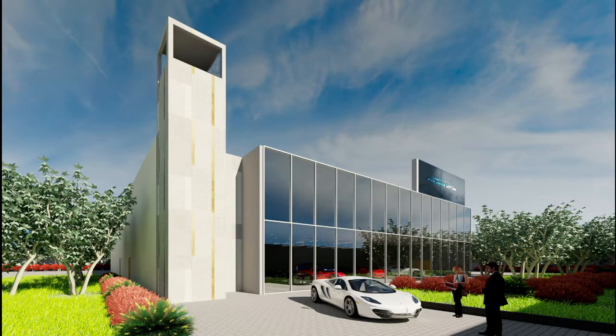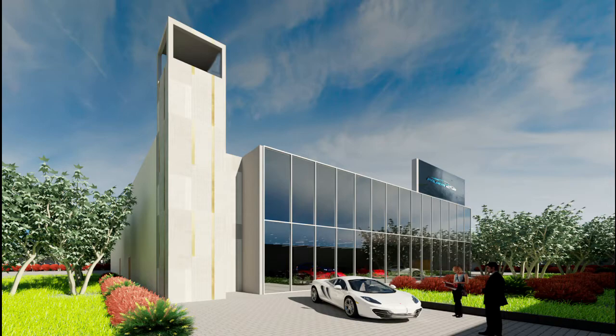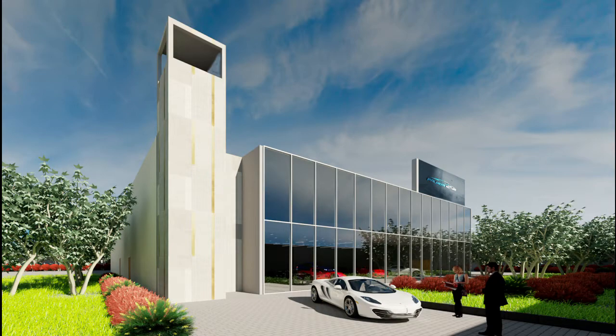Also, the BMS will be programmed to close all gates after hours and turn on the security system to ensure the safety of the building. Finally, to reduce the energy consumption, all auxiliary machines will be automatically turned to low consumption mode when not in use. In addition, the BMS will be monitoring all smart meters such as electricity meters, HVAC link to electricity meter, and smart water meter to analyze consumption and building performance, as well as detecting any abnormalities and defects.